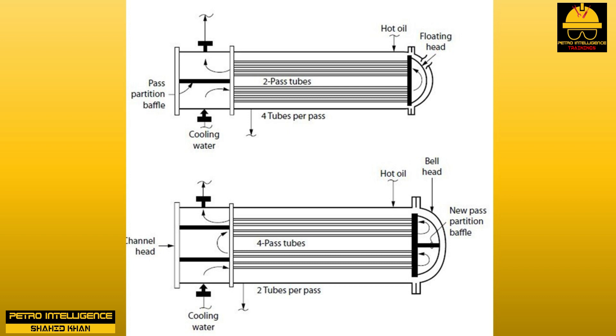The calculations take into account that the water has to flow twice as far through the tube bundle, that there are only half the number of tubes available per pass, but that the water pressure drop must remain constant. Due to the lower flow, the temperature increase of the sea water also went up: two-pass, 70 to 100°F; four-pass, 70 to 150°F. At 150°F, the cooling water precipitated hardness deposits, and the hardness deposits restricted water flow.